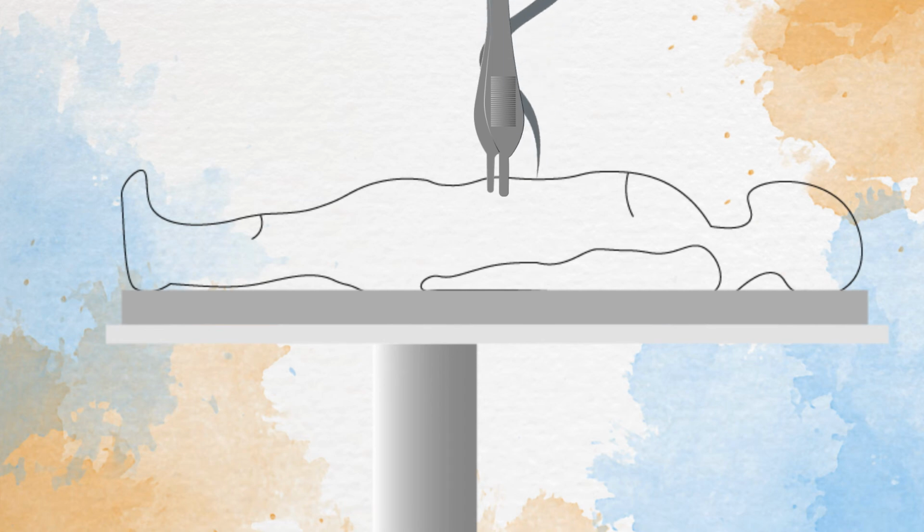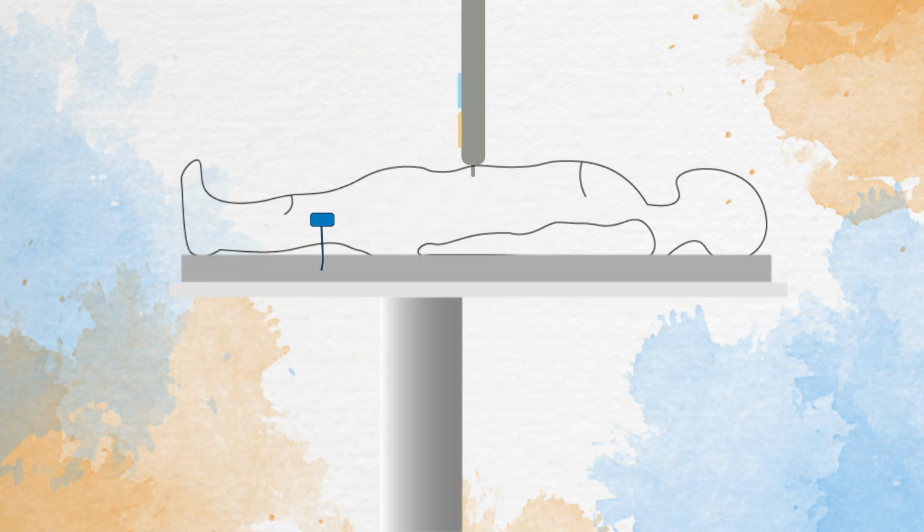Monopolar, on the other hand, has just an active electrode at the surgical site, and the return electrode is actually a large pad placed somewhere else on the body. The return pad is so large that the same power that's spread across a bigger area won't produce as much damage as it does in a confined space right at that active electrode tip.